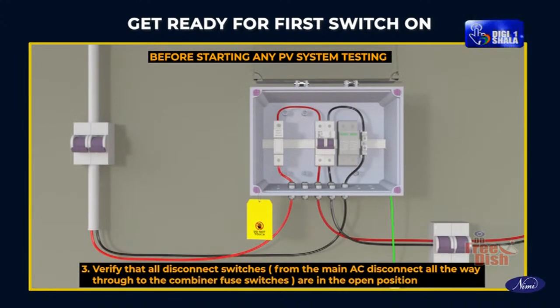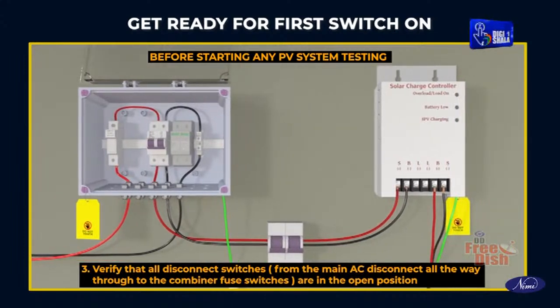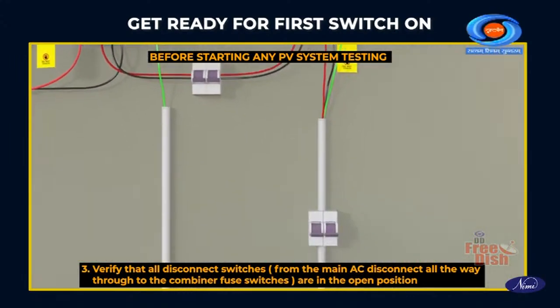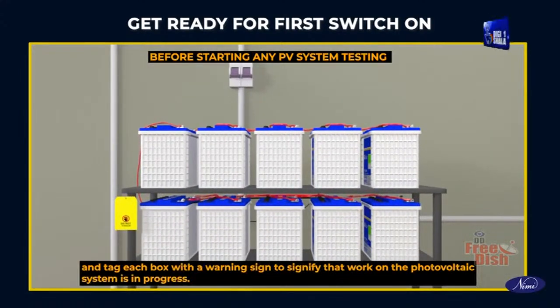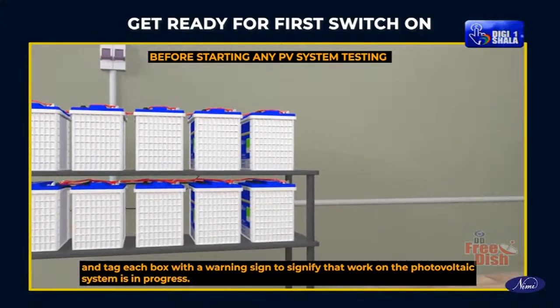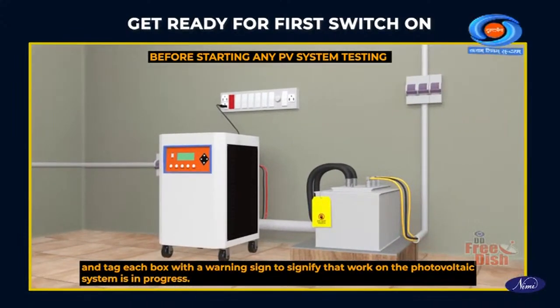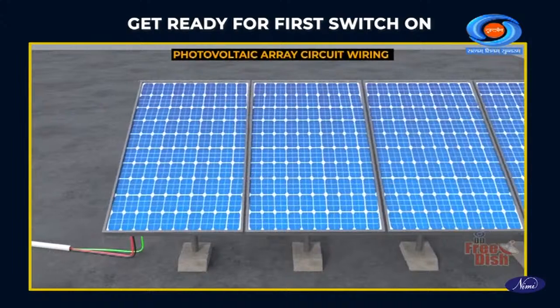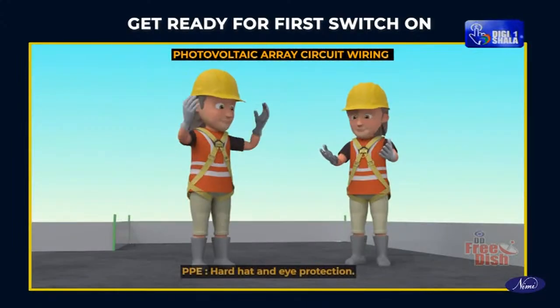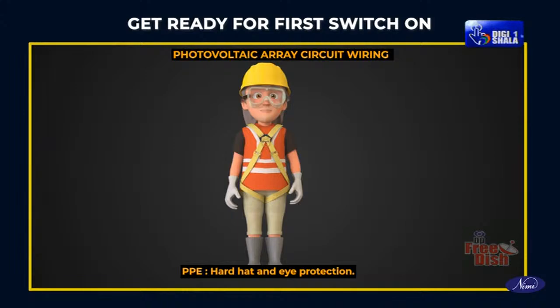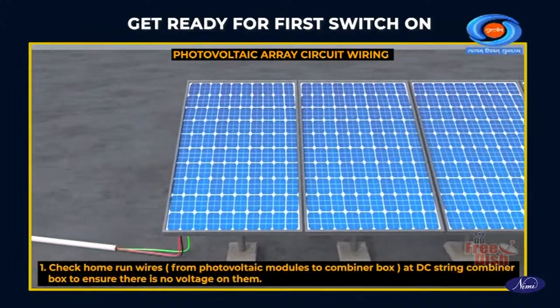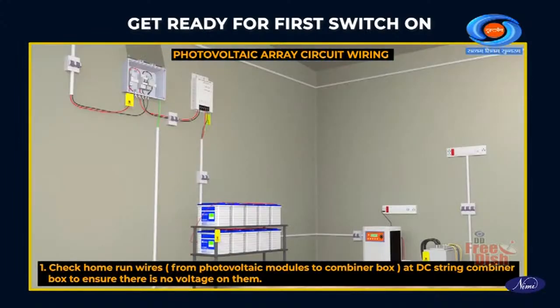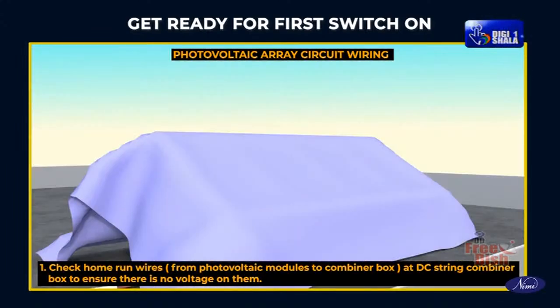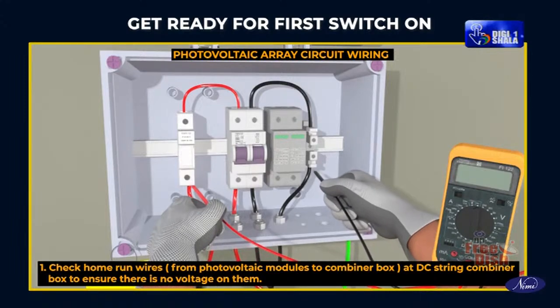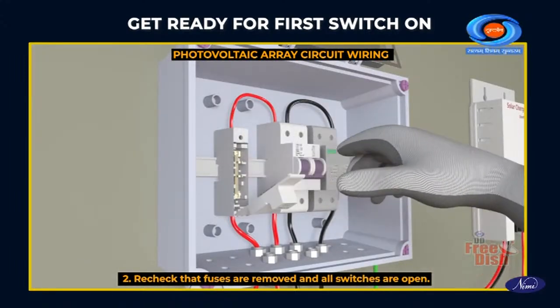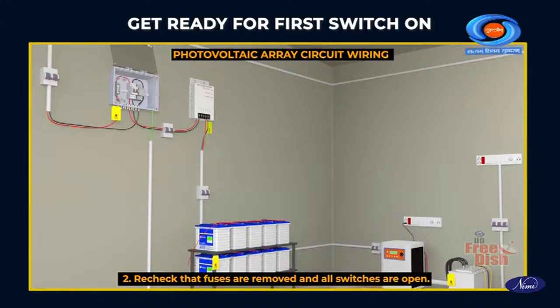Verify that all disconnect switches from the main AC disconnect all the way through to the combiner fuse switches are in the open position and tag each box with a warning sign to signify that work on the photovoltaic system is in progress. Photovoltaic array circuit wiring, PPE: hard hat and eye protection. Check home run wires from the photovoltaic modules to combiner box at the DC string combiner box to ensure there is no voltage on them. Recheck that fuses are removed and all switches are open.